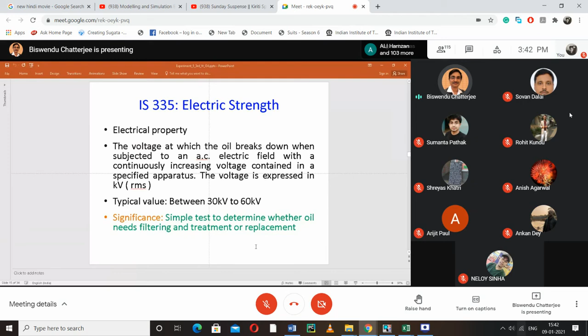Now comes the electric strength. In this experiment we will measure the voltage at which the oil breaks down when subjected to an AC electric field. Typical values are between 30 kV and 60 kV. 60 kV is a good oil. At 30 kV, the oil has gone to its lowest, or is deteriorated to its extreme negative end. And the significance is a simple test to determine whether the oil needs filtering, treatment or replacement. Now we go to IS 6792.